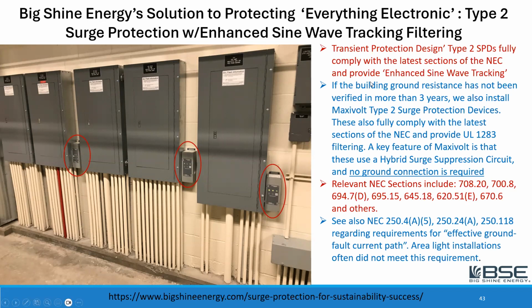If you put one type 2 surge protection device on a given panel, it will protect all of the electronic loads on that panel. The only requirement is this Transient Protection Design device does have to be connected to a very effective earth ground. If there's a concern about the ground and we can't verify it, there's another device that we use. It's made by a company called MaxiVolt. This has a very unique feature called a hybrid surge suppression circuit, and it doesn't require a connection to ground. So it's able to suppress these spikes and voltage disturbances, even if the ground isn't adequate. So MaxiVolt is a great way to take care of a system where we can't verify, or don't have time to verify, that the grounding is effective.